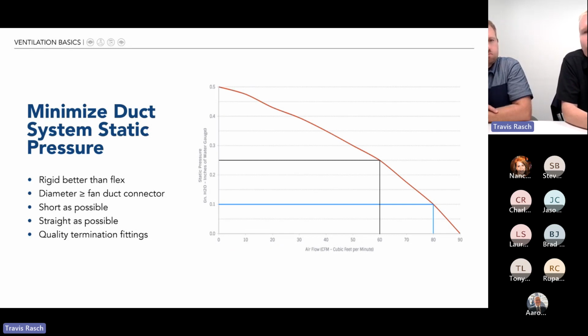But it's becoming more and more important. If you look up at the 1/4 inch level there, that other black line, follow it to the fan curve and drop it down. This fan only moves 60 CFM at a 1/4 inch. A 1/4 inch is much more realistic static pressure. Most of the codes today, when they say how to check how much airflow you're getting out of a mechanical ventilation device, they say look at its 1/4 inch static pressure, in the case of a bath fan or hood.